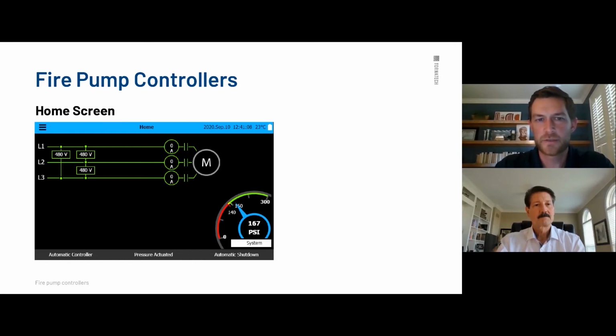Then you'll see L1, L2, L3 right below that. That's going to be line 1. This is our normal power, and we're showing 480 volts. That is taking 3 different readings. So you're going to get a reading from line 1 to line 3, and that's 480. Then you'll see line 1 to line 2, and line 2 to line 3. So we're monitoring all 3 phases of power coming in at all times. And one note here on the ViZiTouch: green is good, yellow is cautionary, and red is bad. So we've tried to color coordinate things based on green being good, red being bad. You can follow the green line here saying that power is healthy.